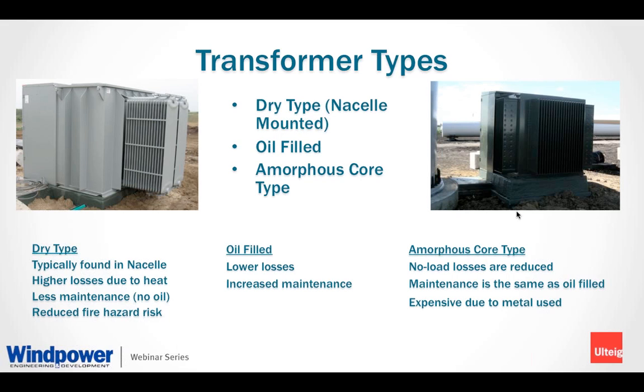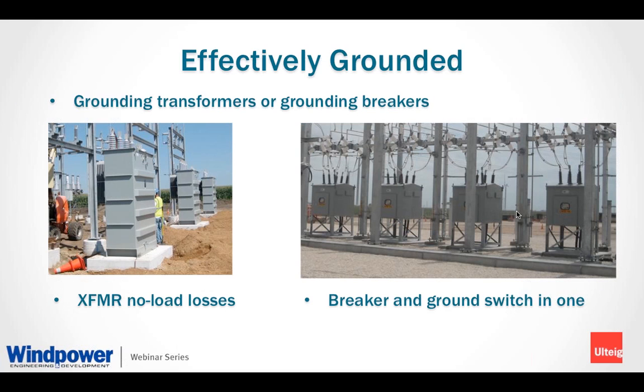Another thing you can consider within all these types of transformers is aluminum versus copper again. There are many manufacturers who have different designs and different ways of doing things, especially with the transformer core type. A significant benefit is aluminum can be lighter, but the transformers are going to be larger. Copper is obviously going to be heavier, but it's going to be smaller. So, depending on the market, aluminum may be cheaper versus the copper too. So just some more things you want to consider.